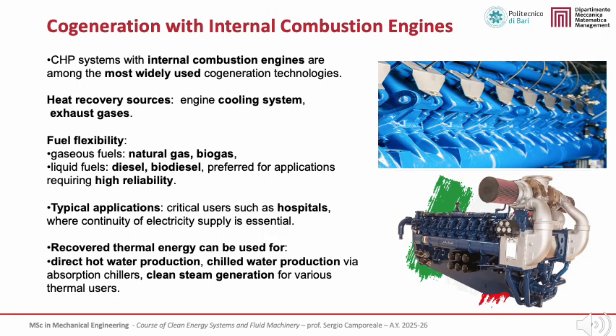In terms of fuel flexibility, spark ignition engines typically operate on natural gas or biogas, while compression ignition engines can use diesel or biodiesel, and are often preferred in applications requiring very high reliability. Typical applications include critical users, such as hospitals, where continuity of electricity supply is essential and on-site generation provides additional resilience. Recovered thermal energy can be used for direct hot water production, chilled water generation via absorption chillers, or clean steam production for various thermal users.